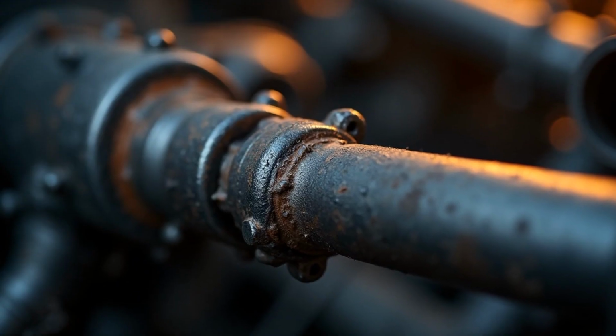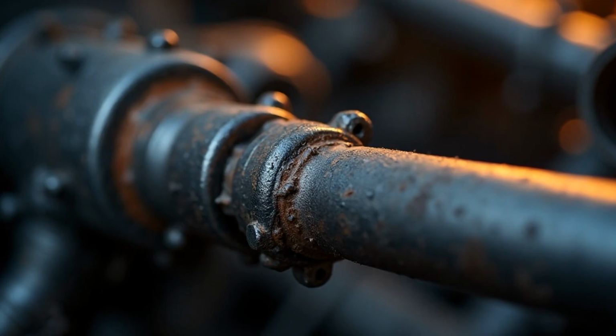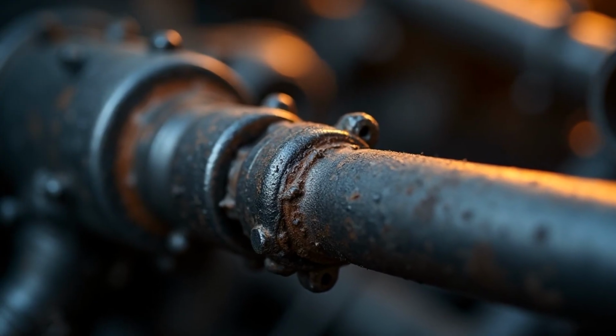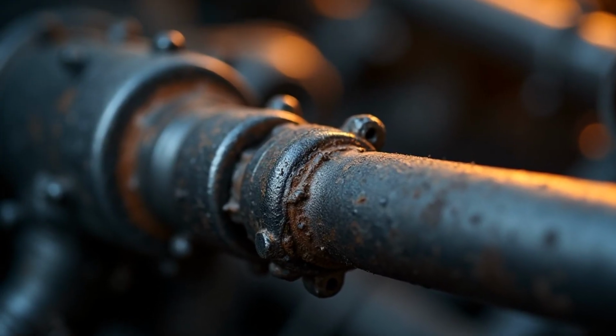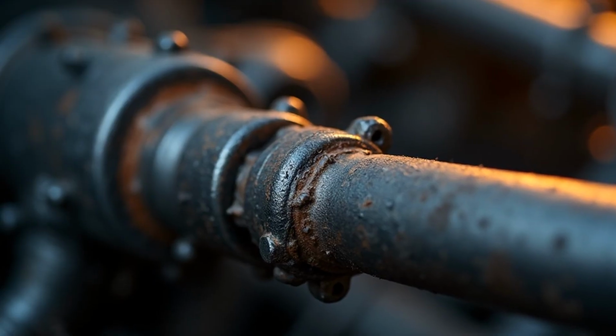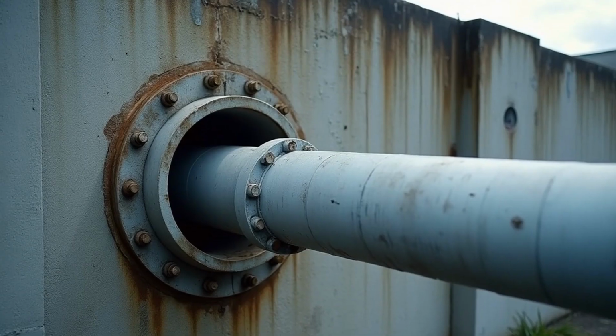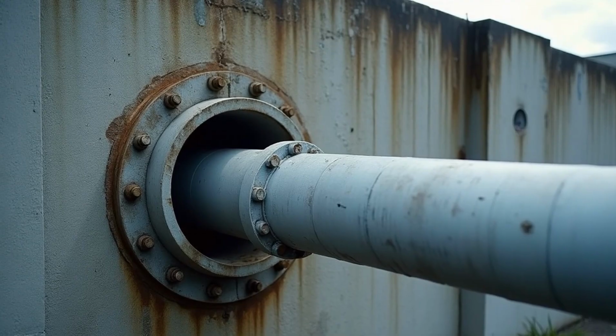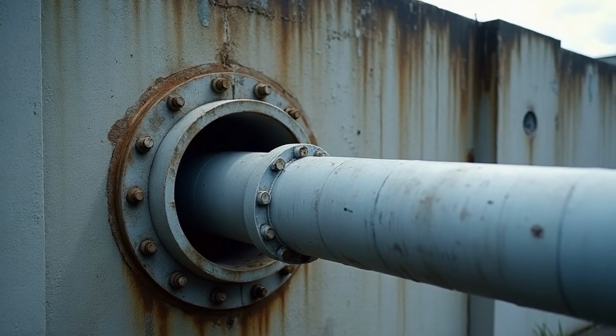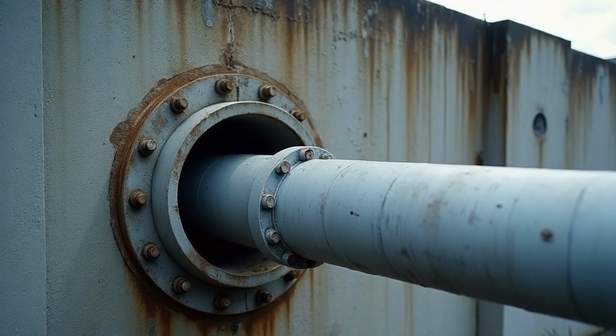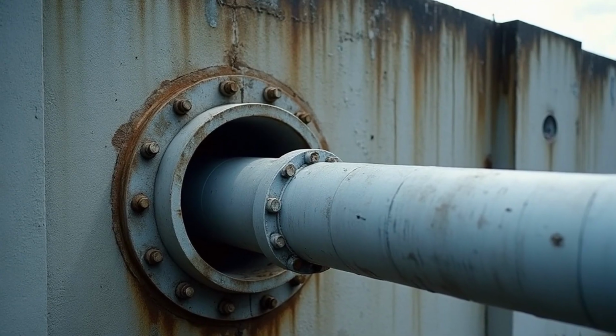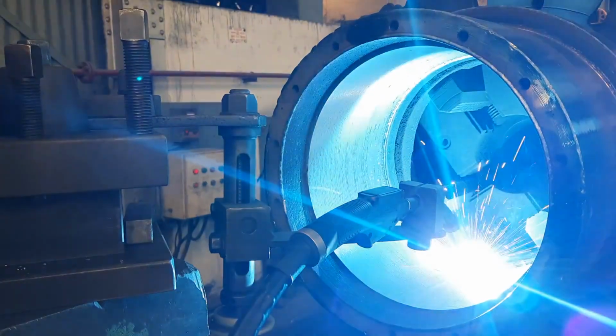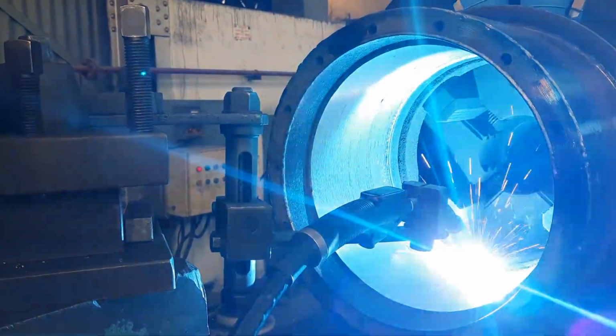Now bring back the liquid loop, because it genuinely helps. Water leaving a cold plate is warmer than any air-cooled hall manages. Warm, not hot, but warmer, cleaner in one place, moving at a known rate. For reuse, a real improvement. And it is still not enough.